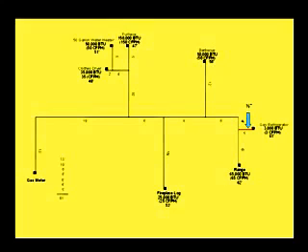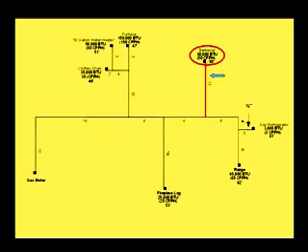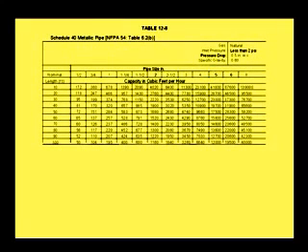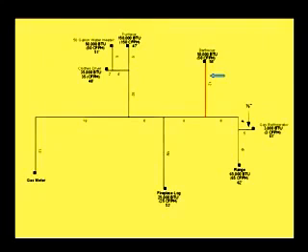The 12-foot section for the barbecue is next and has a demand of 50 cubic feet per hour and is 58 feet from the meter. Refer to table 12-8, 60-foot row — 50 will fit under 65 — and see that a 1/2-inch pipe will accommodate the 50 cubic feet per hour demand for the barbecue.